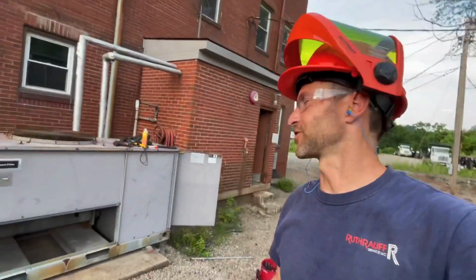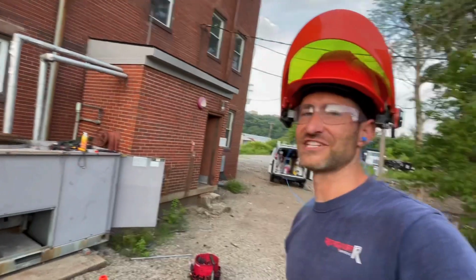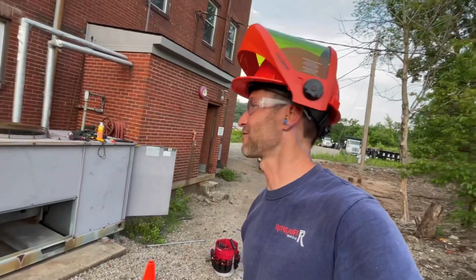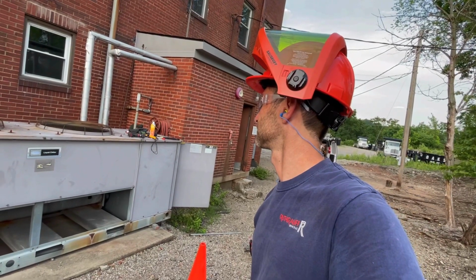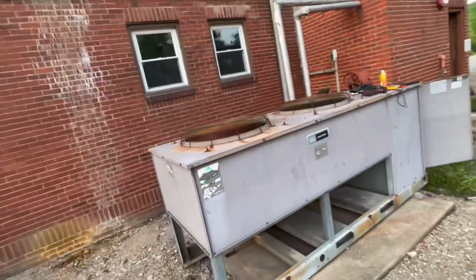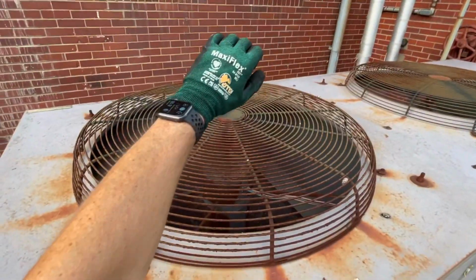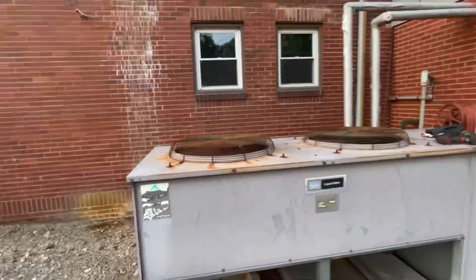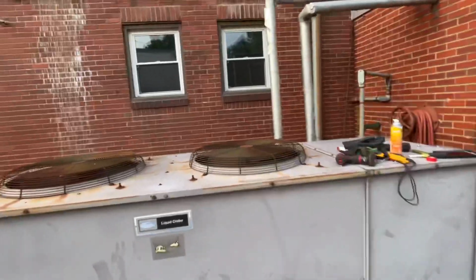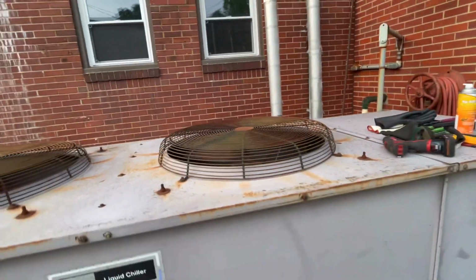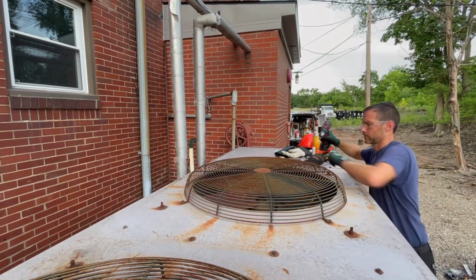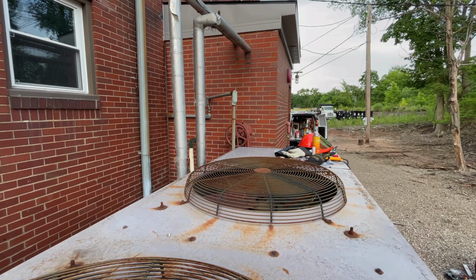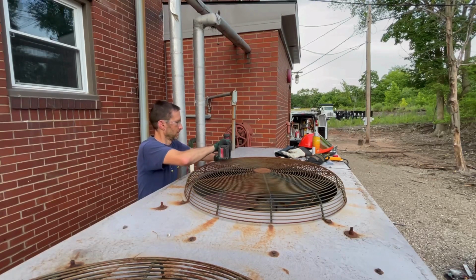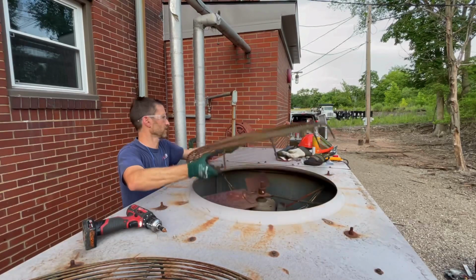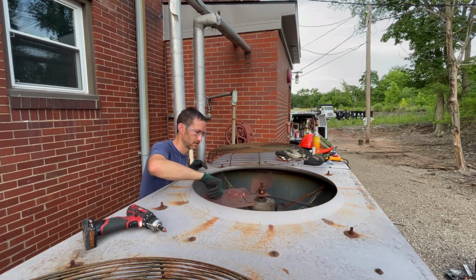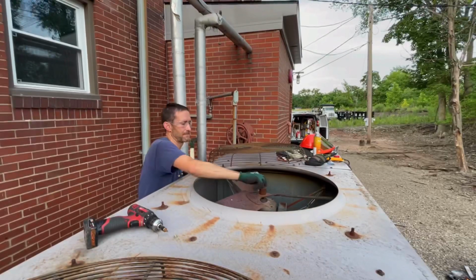It was tripping out on high pressure, and it was going into alarm, and maybe that mouse didn't cause it. Either way, we had to get that mouse out of there. We had to fix that wire. It was going to short out eventually. It's getting hot, people. Oh, she's getting real hot. Yeah, let me shut this down. This fan should be kicking on by now. I just have a suspicion, guys. We either got an open motor or maybe a wire burned off. By the looks of all this rust, it might be an original motor. Power's off, everything's dead. Oh. Bad bearings. Bad bearings, it's got an open winding, almost guaranteed.